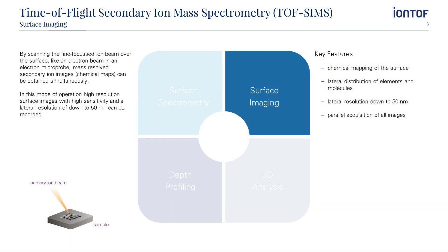By scanning the fine-focused ion beam over the surface, like an electron beam in an electron microscope, mass-resolved secondary ion images — chemical maps — can be obtained simultaneously. In this mode of operation, high-resolution surface images with high sensitivity and a lateral resolution of down to 50 nanometers can be recorded. You can see the lateral distribution of elements and molecules, and due to the parallel mass detection of the time-of-flight analyzer, all images of all different masses can be acquired simultaneously.